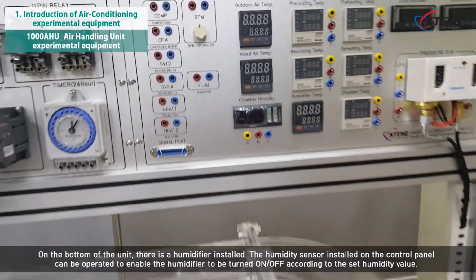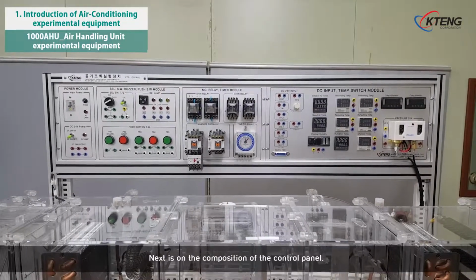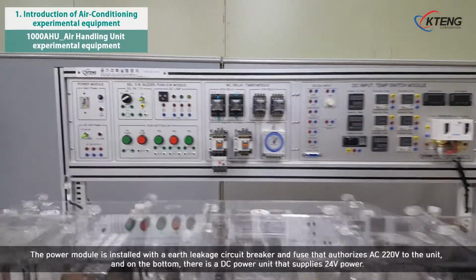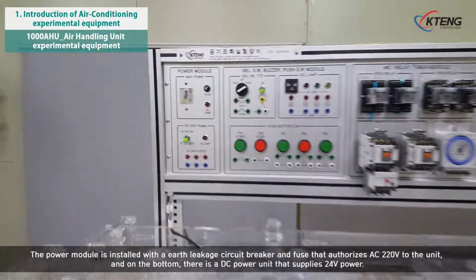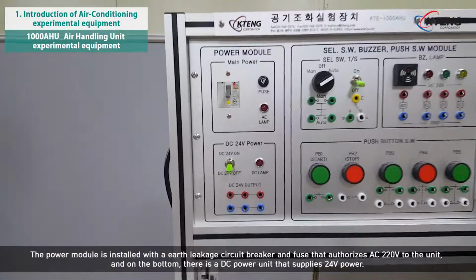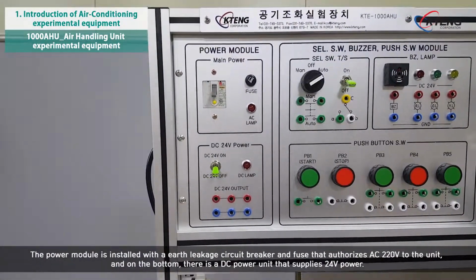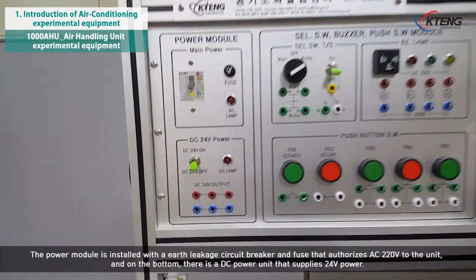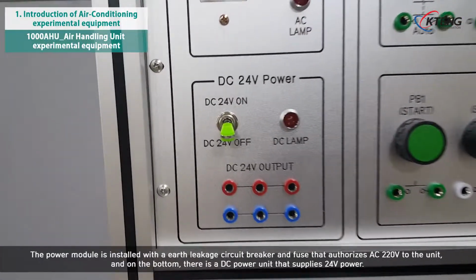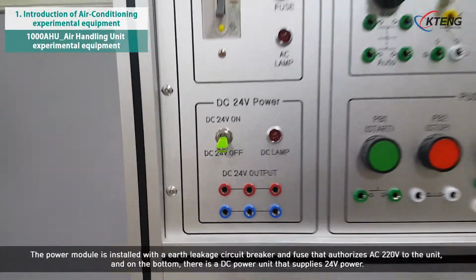Next is on the composition of the control panel. The power module is installed with the earth leakage circuit breaker and fuse that authorizes AC 220 volt to the unit, and on the bottom, there is a DC power unit that supplies 24 volt power.